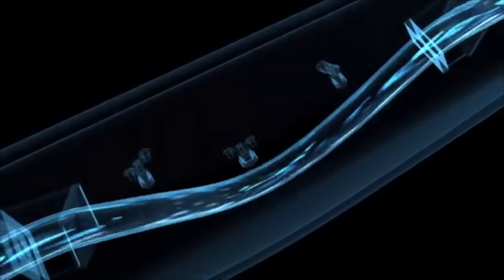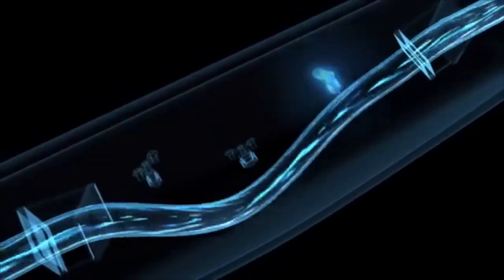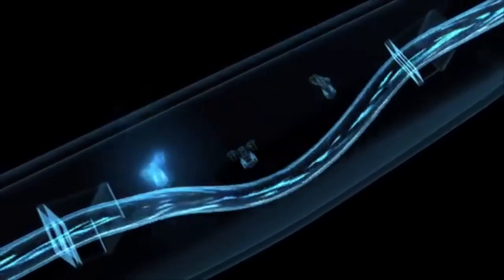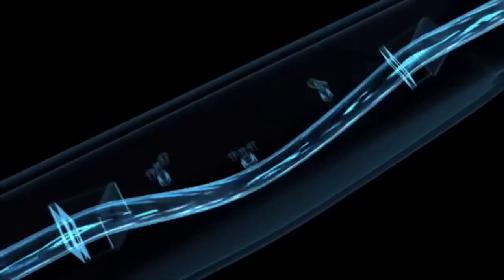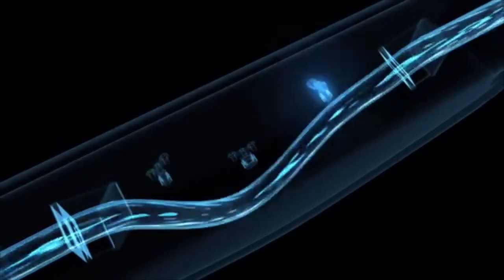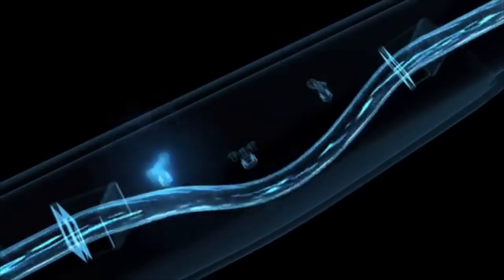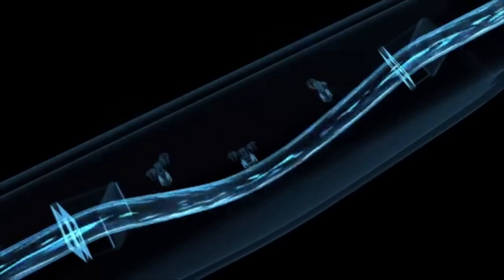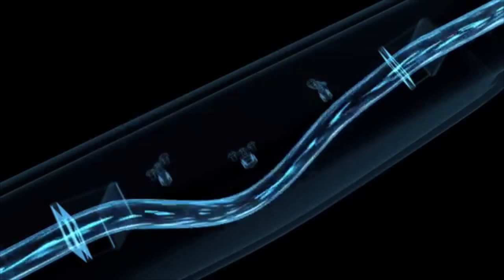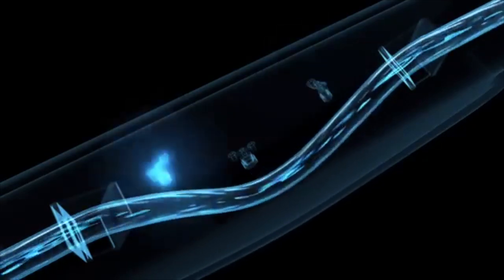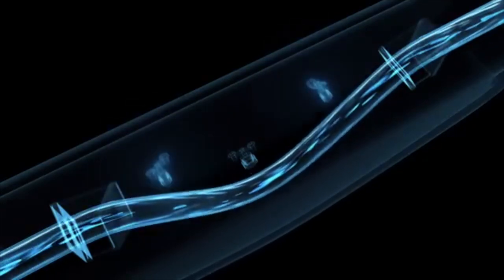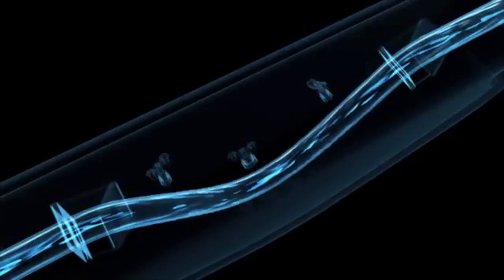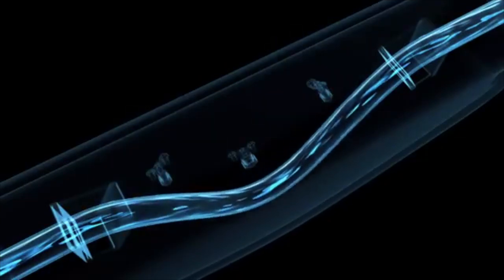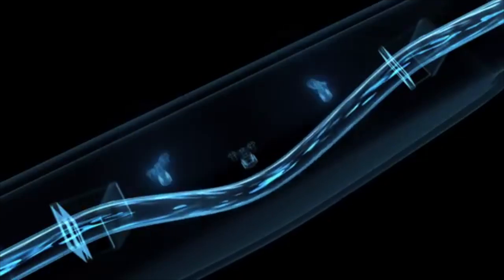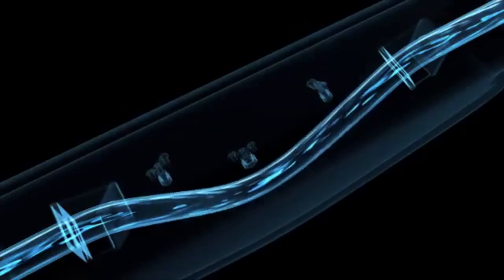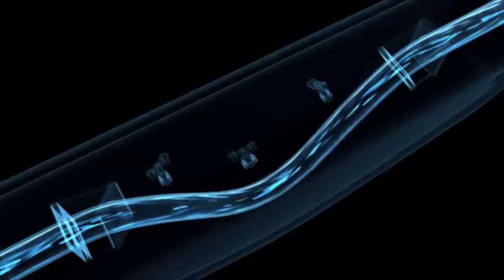The higher the flow velocity and thus the total flow, the greater the deflection of the oscillating measuring tube. The application of the Coriolis measuring principle does not stop here. It can also be used to simultaneously determine the density of the flowing fluid. To do so, the sensors are also registering the oscillating frequency, in other words, how often the tube moves back and forth in 1 second.